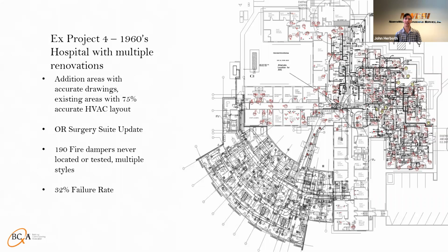I can't tell you guys enough, if you find yourself in this situation doing the investigation side to find out how many devices are in the field, you have to set the expectation that you're likely going to find more. It's just what happens. So on a T&M basis, you say, okay, our scope is to find 30, we can test 30 under that. But if we start finding more, I'm going to let you know immediately, and I'm going to let you know if we can cover that extra 5, or if it's an extra 20 that we can't cover.